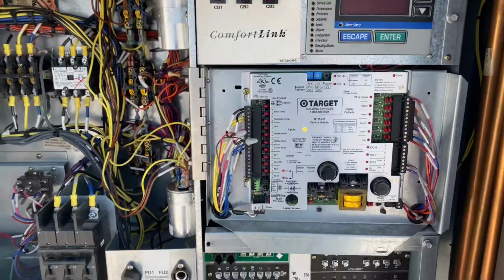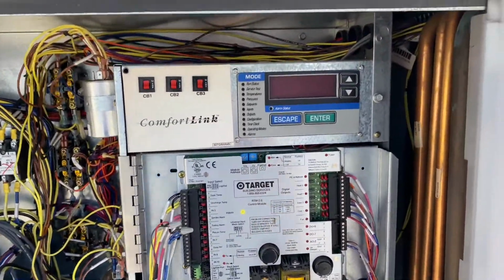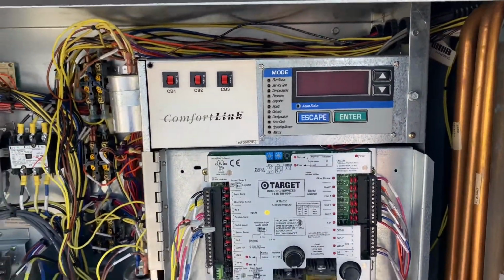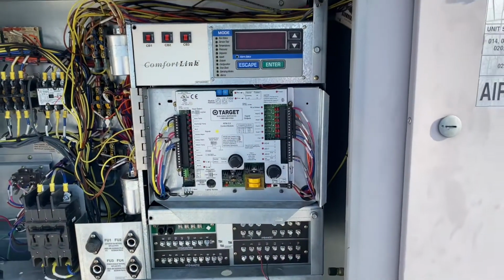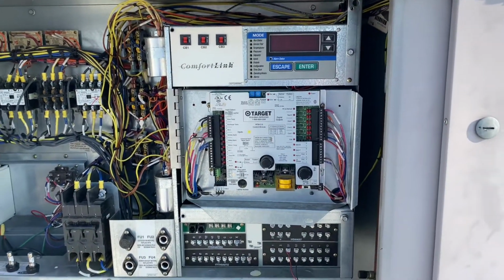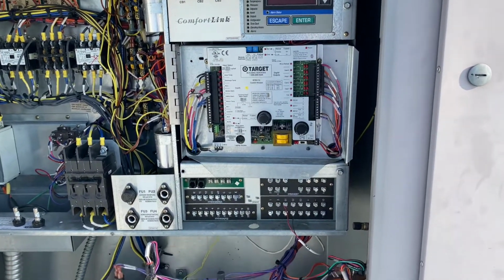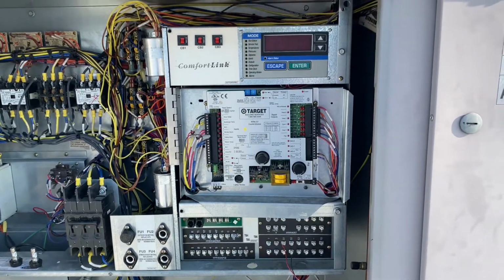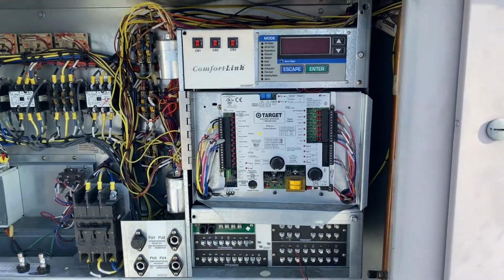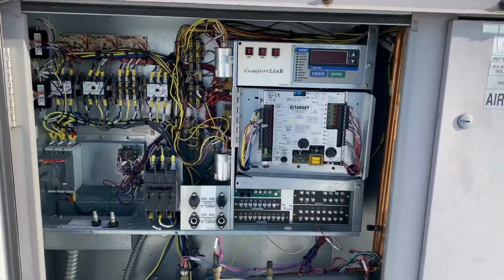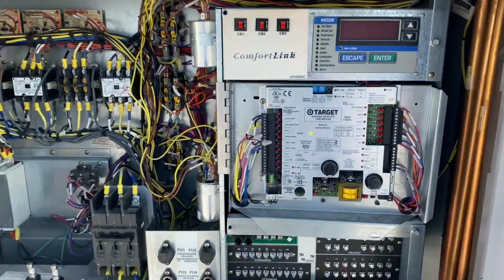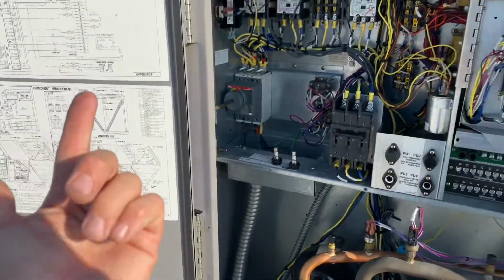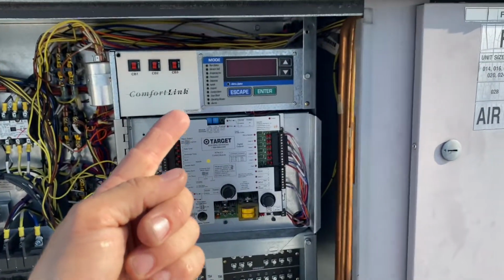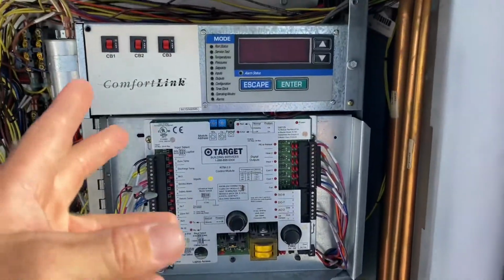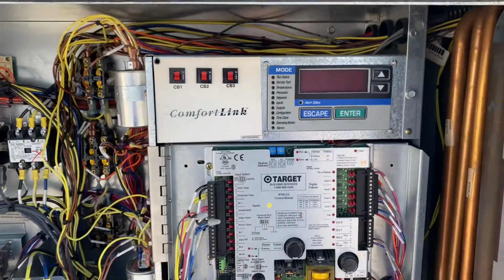Like I say, get it in test mode as quickly as possible, and then test the fans and see if one of them pops the fuse. If one of them pops the fuse, I've got plenty of spares, but at least it gives me a starting point. We'll go from there. All right, so my plan worked out well. I was able to get power kicked back on and quickly get over to the controller. It was getting power, which is good. It was getting its 24 volt power.